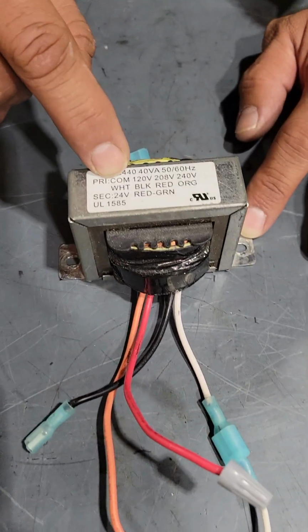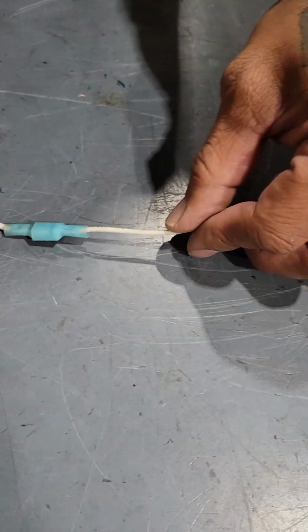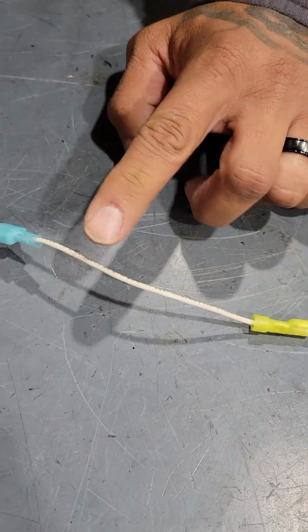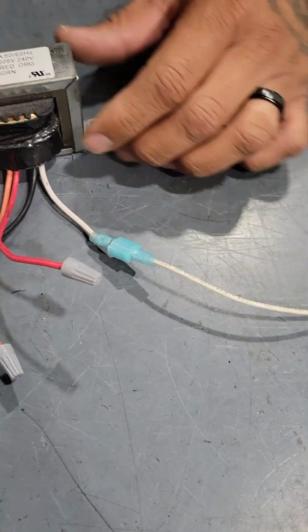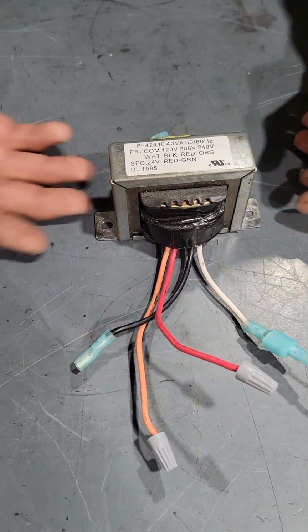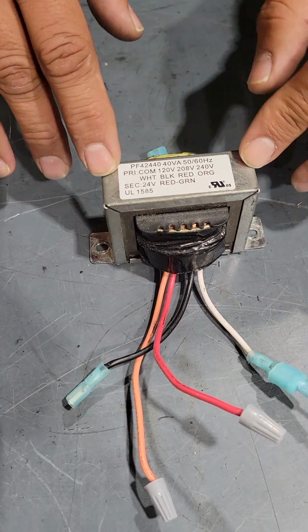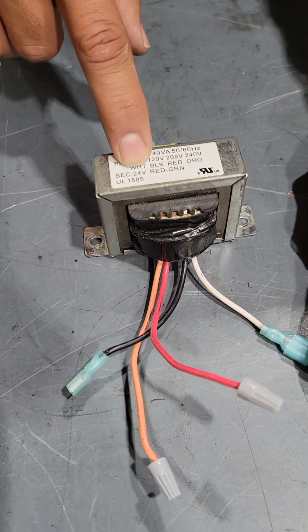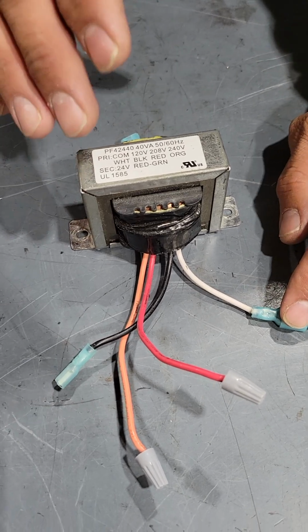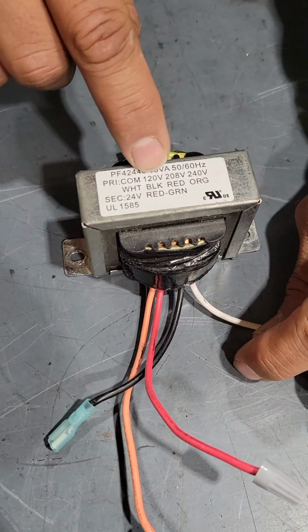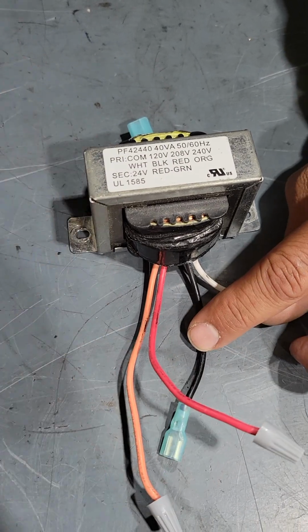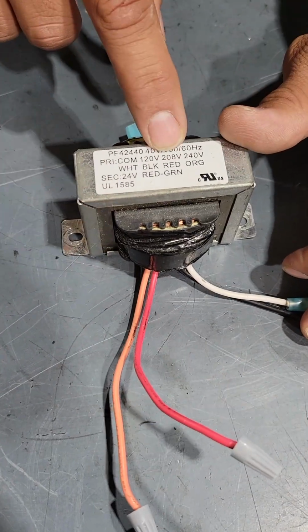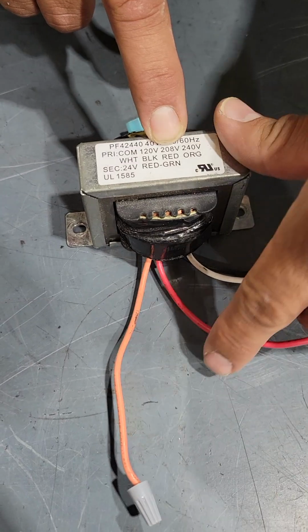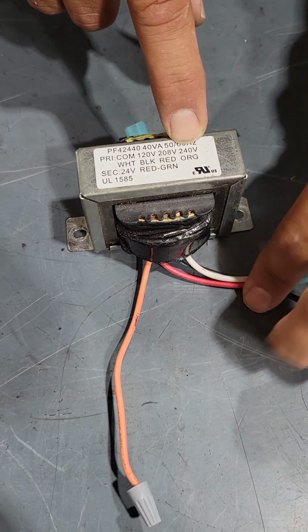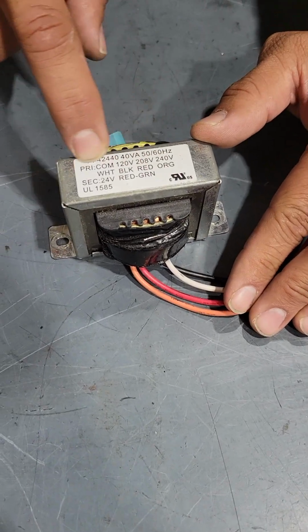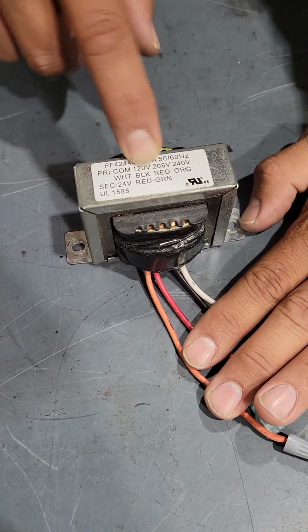Okay, it tells you right here, your common wire is always going to be, and again, these wire colors may change depending on what brand of transformer you use. Every manufacturer is different, but this one is using the common as your white wire, and they'll always tell you, as long as you read it, your 120 volt tap is going to be the black wire. 208 volts is going to be your red one, and then 240 volts will be your orange one. And that's going to be your primary side. That's where all the line voltages will go.